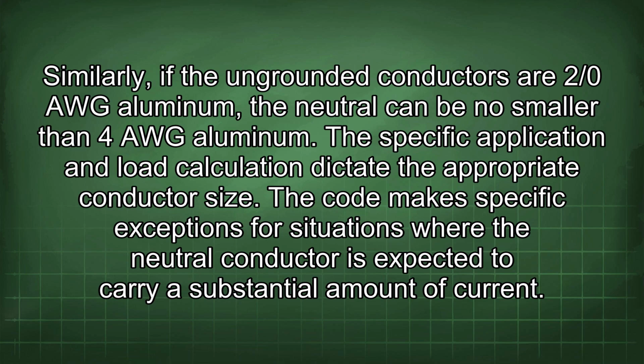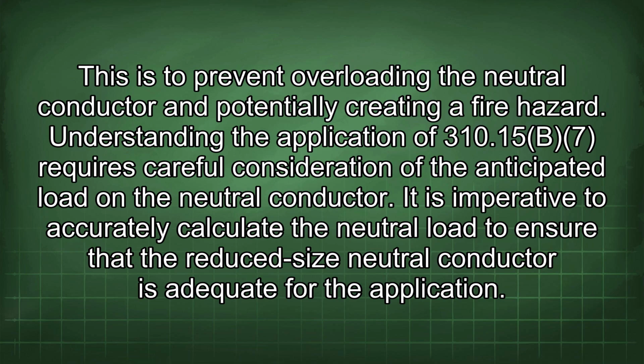The code makes specific exceptions for situations where the neutral conductor is expected to carry a substantial amount of current. This is to prevent overloading the neutral conductor and potentially creating a fire hazard. Understanding the application of 310.15(B)(7) requires careful consideration of the anticipated load on the neutral conductor. It is imperative to accurately calculate the neutral load to ensure that the reduced size neutral conductor is adequate for the application.